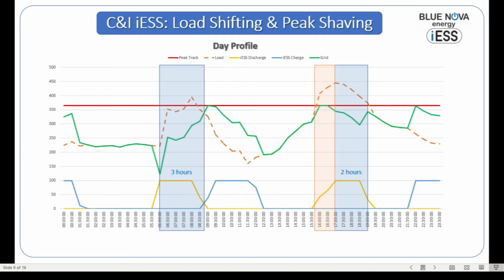And one can see that during the first 3-hour peak period, we are doing a controlled discharge and also making sure that the peak around, I think it's 8 o'clock in the morning, is also shaved off. Then we maintain the energy consumption below that peak. And then one can see that before the 6 o'clock to 8 o'clock discharge, from 5 in the afternoon, we're also doing a controlled discharge and then continuing with that discharge from 6 to 8 in the evening. So it is a hybrid result that we see in this picture of both peak shaving and load shifting happening simultaneously. And one would obviously want to optimize this for the maximum use of the energy storage device, controlling the total discharge for the day at 80% of the installed capacity of the iESS system.